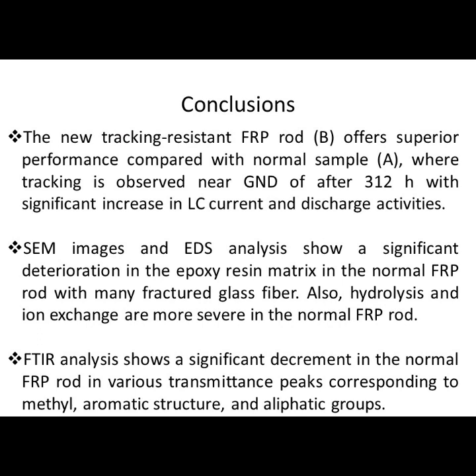This slide shows the conclusions of the work, where the new tracking resistant FRP rod shows a superior performance compared with the normal FRP rod, where tracking takes place in the normal FRP rod after about 300 hours near the ground electrode with a significant increase in the leakage current and also the discharge activities. Both SEM, scanning electron microscope, and energy dispersive X-ray spectroscopy analysis showed a significant deterioration in the epoxy resin matrix in the normal FRP rod with many fractured glass fibers, and also hydrolysis and ion exchange were more severe in the normal FRP rod.